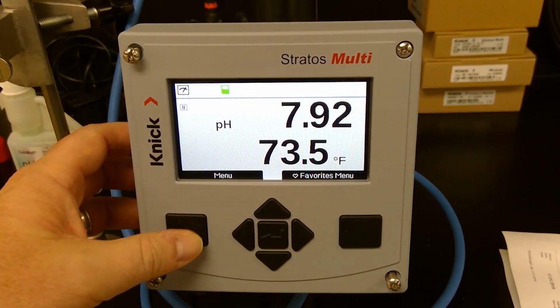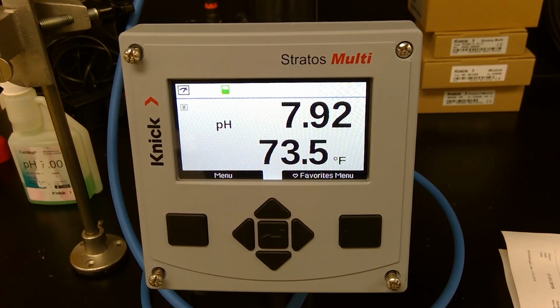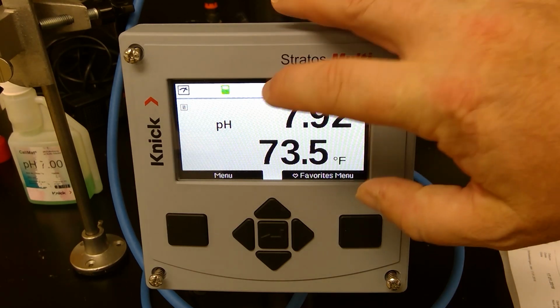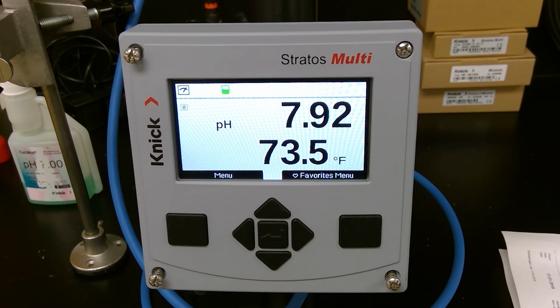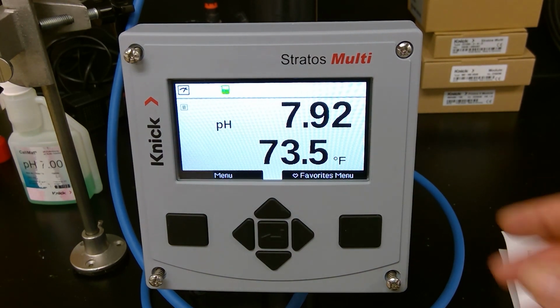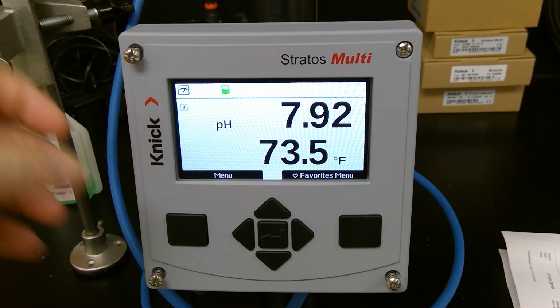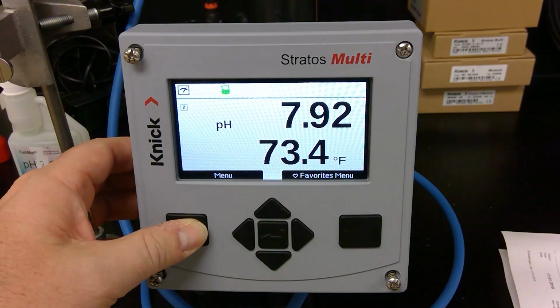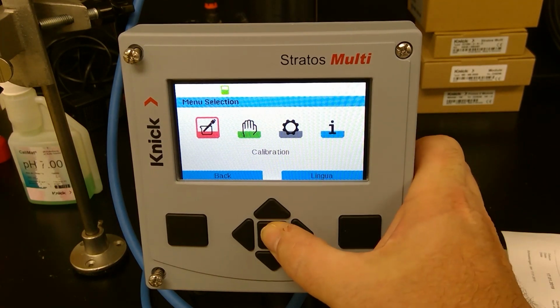So of course at this point you're taking your grab sample, you're going back to the lab, whatever the case may be, but you'll notice while you're gone, this little calibration beaker is going to be on the top of the screen indicating that it's currently in a process calibration. So it's waiting. Now it's going to function, it's still going to read, but it's waiting for someone to come back and finish that process cal.